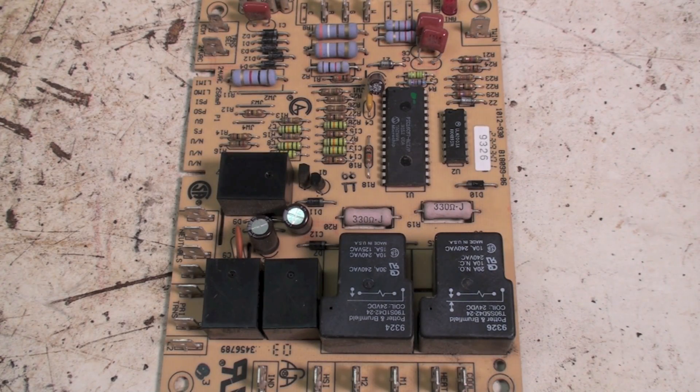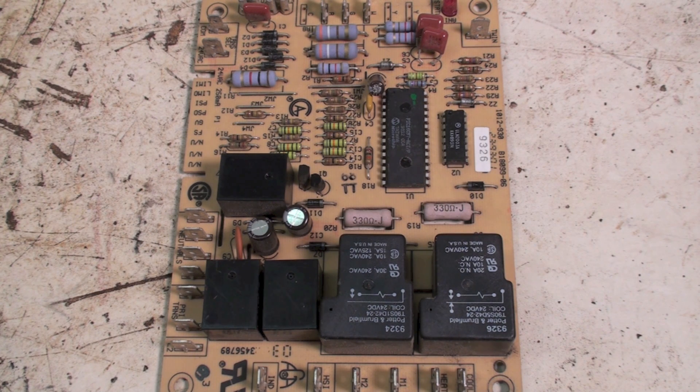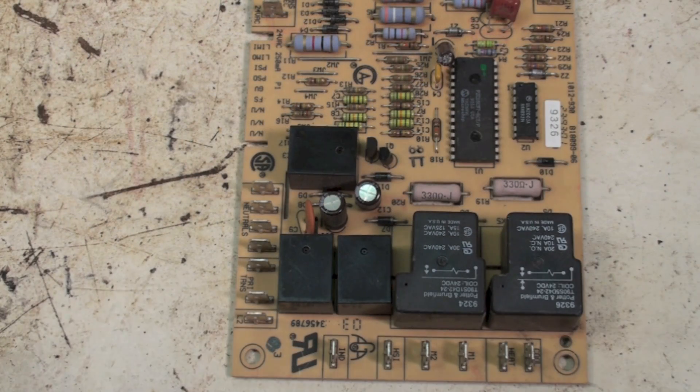Before we do any motor speed changes, be sure you've cut your power from the furnace. When you took the furnace door off it should have shut it off with the door switch, but they're not always hooked up. So make sure your power is off. Here we've got an IFC and the fan motor wires are hooked here.